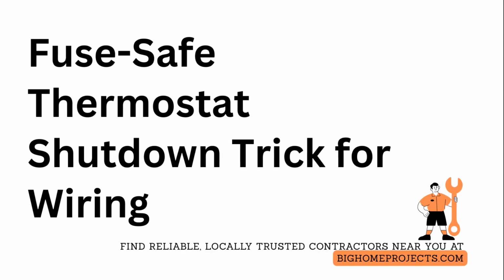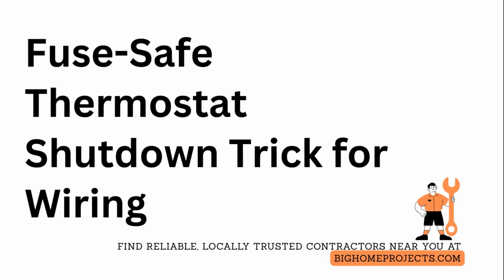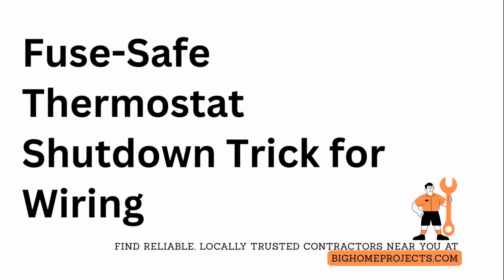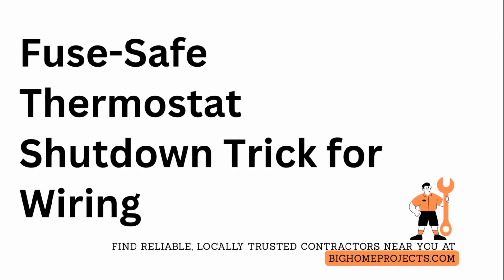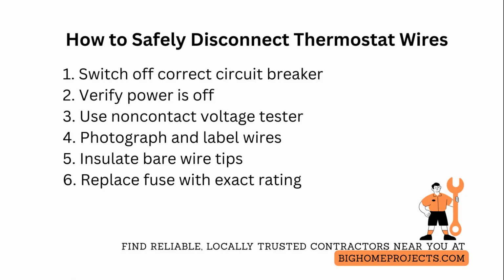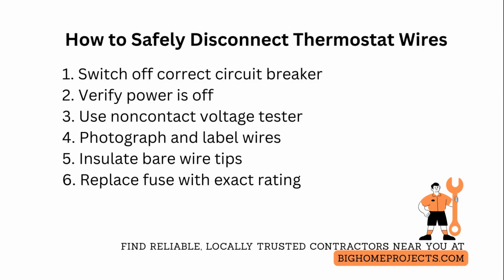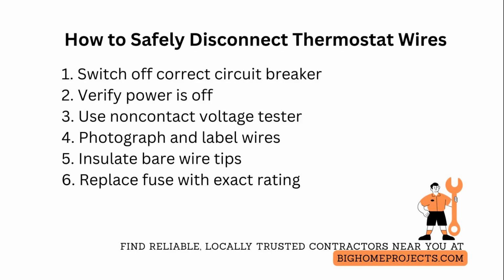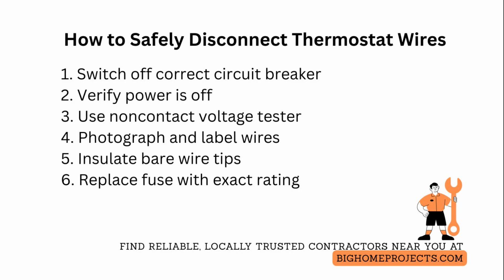Turn off all power to the heating and cooling system at the breaker before touching thermostat wires to prevent shorts and blown fuses. When replacing or installing a thermostat, first locate and switch off the correct circuit breaker for the furnace or air handler at the electrical panel, and verify power is off by testing the thermostat display and the unit itself. If the thermostat is powered by a separate 24-volt transformer, also turn off the furnace door switch or remove the fuse in the furnace control board to completely isolate the control circuit.